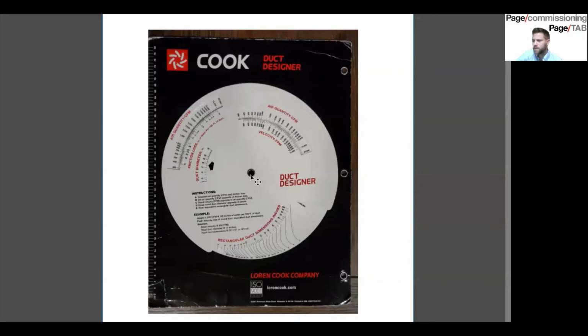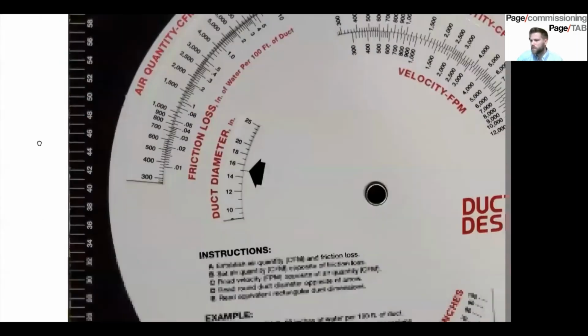You can also do it straight off your computer. A lot of people have Excel files that can do it. But I like these guys. And basically the way that you're going to do it is you have your friction loss over here. From this picture, you can see the 0.08, right? And that's what you would use to size your ductwork. So you just line that up, and then you're seeing that you can do 1100 CFM at 0.08.